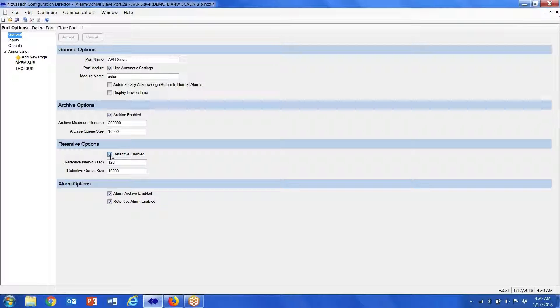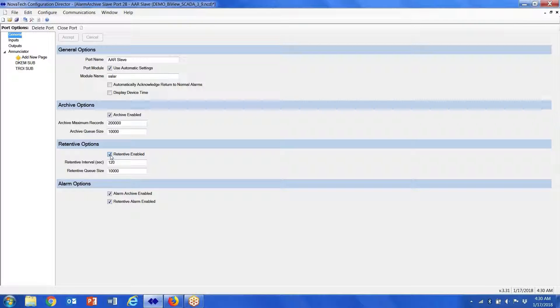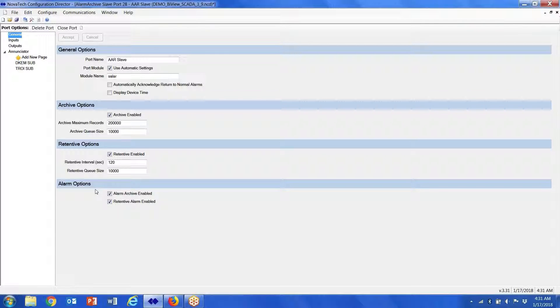So that when the Orion reboots, if you've got a logic point that you've created and you want the Orion to retain that last known state when it comes back online, that's what the retentive allows you to do. Archive allows you to archive points that are in the database, and the alarm option allows you to create points in the database and then go to an alarm screen.